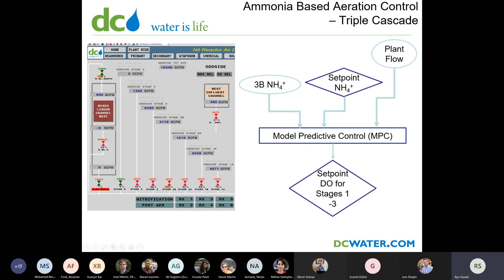There are a lot of different types of MPC out there, but the particular one that we have is a strictly empirical controller. So the way you tune it is, on a given day, first you set your DO constant, and you monitor how the effluent ammonia changes as the plant flow changes. So that's one of the tuning parameters. On the following day, you try to find a time when the plant flow is constant, and you make step changes to the DO and see how the ammonia reacts. Based on those two kinds of empirical real-time data, the controller gets updated and tuned. So a little bit different from your typical PID loop.